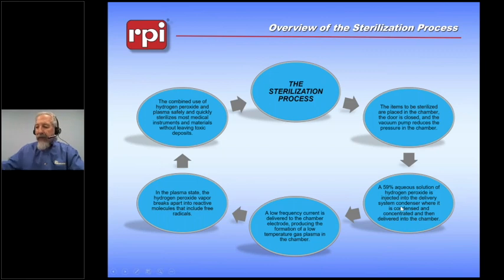Okay, so what are we talking about here? This is the actual cycle that the users will be doing. Again, we talk about how they make sure that the material is in the chamber, that it's pumped down, the aqueous solution of peroxide is put into a vaporizer, and then it's concentrated and delivered to the chamber. We take that peroxide, we apply a plasma to it, or turn it into a plasma using a current generator that's delivered onto the material, and the peroxide breaks apart, and the combination of peroxide and oxygen is what does the sterilization without leaving residue. Next slide.